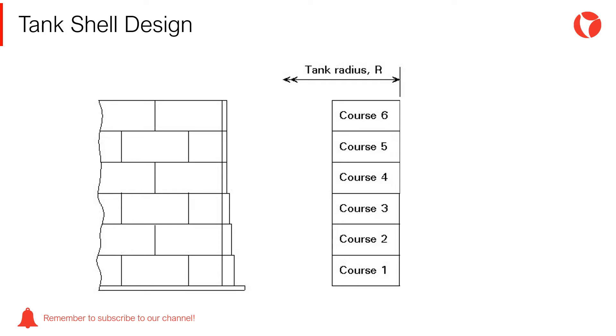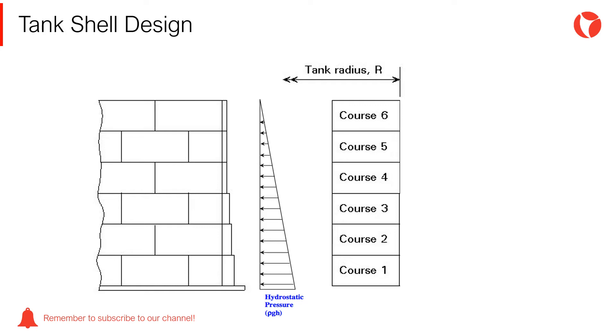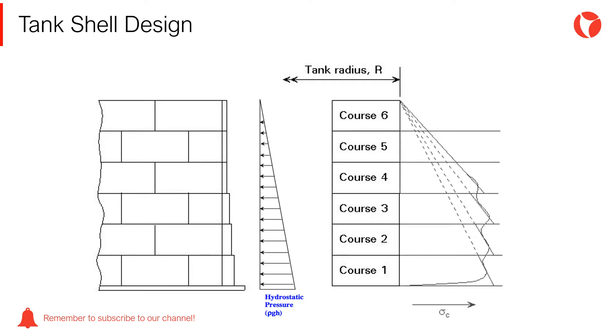It is clear to observe that the hydrostatic pressure will be maximum at the bottom of the tank due to higher static head. Therefore, the bottom shell courses will require a thicker plate, decreasing moving upwards in the tank shell. Circumferential stresses induced in the tank shell due to the hydrostatic pressure are not linear, mainly due to the presence of welded joints having higher allowable stresses than plates. Consequently, the stresses in one shell course is not linear either, having its maximum value at a certain height.